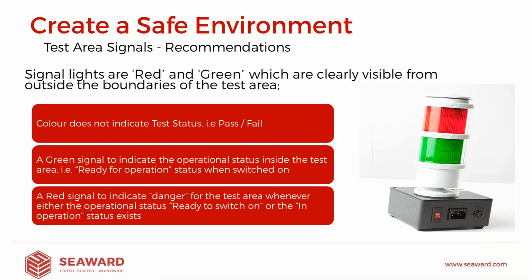For those of you that do have Seaward testers, we always install a point at which you could plug an off-the-shelf beacon into the tester, and that takes a signal directly from the high voltage output. So as soon as the voltage hits unsafe levels, i.e. 25 volts AC, 60 volts DC, the tester will switch the beacon up to red to alert everyone that potentially unsafe voltage is present.